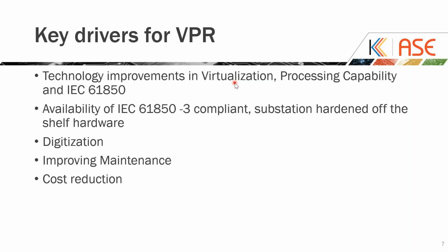With all these increased processing capability, with new generation server hardware, these relays can handle complex algorithms and tasks with higher speed and accuracy, ensuring reliable protection for electrical systems. There's hardware designed to withstand harsh substation conditions, compliant to the IEC 61850 standard, and accessible for use in virtual protection relay systems currently.